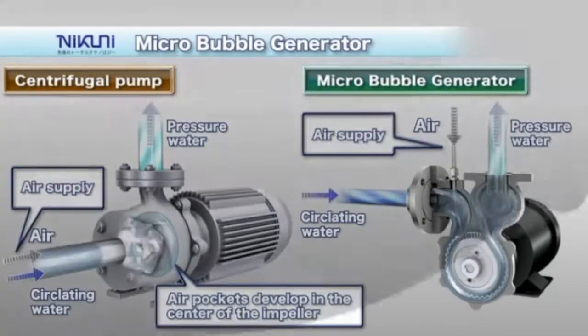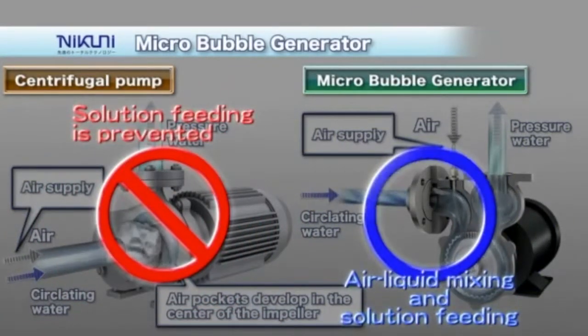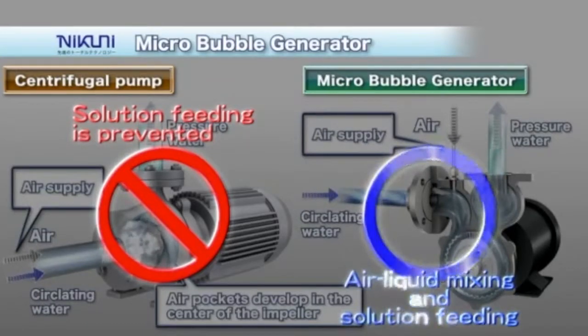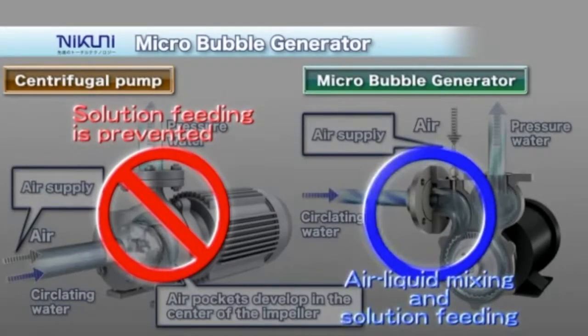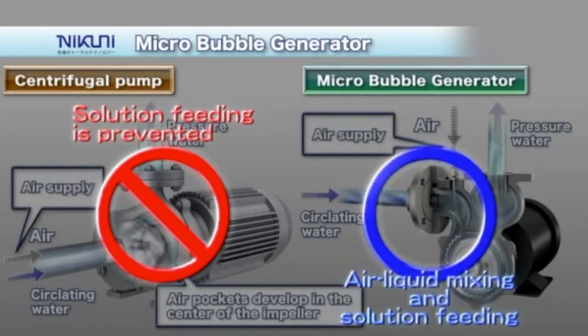The Nikuni KTM micro bubble generator uses a turbine mixing impeller to dissolve the air that has been drawn into the suction port, and then feeds the solution continuously under high pressure to your process.